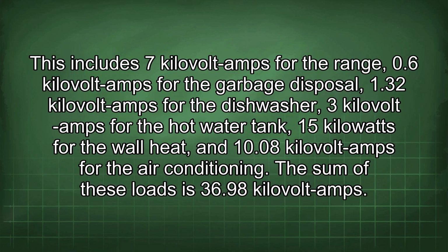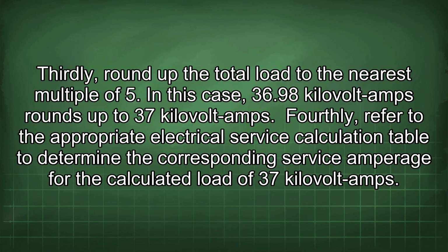This includes 7 kVA for the range, 0.6 kVA for the garbage disposal, 1.32 kVA for the dishwasher, 3 kVA for the hot water tank, 15 kilowatts for the wall heat, and 10.08 kVA for the air conditioning. The sum of these loads is 36.98 kVA. Thirdly, round up the total load to the nearest multiple of 5. In this case, 36.98 kVA rounds up to 37 kVA.